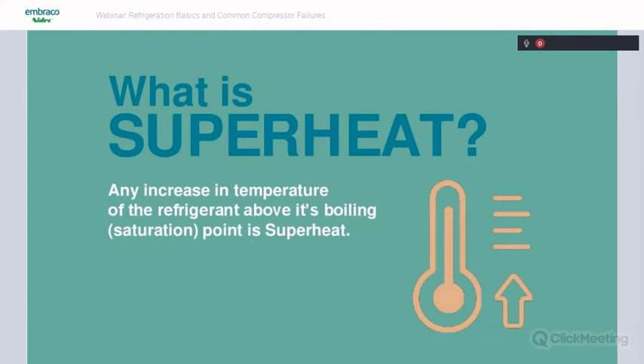Like right now, what is superheat? Superheat is any increase in the temperature of the refrigerant above its boiling point. We also call that boiling point the saturation point. So anytime a liquid gets enough heat in it to where it boils, that's what we call the saturation point. And you can use that to charge a system. Typically, we're going to want to use superheat in a fixed orifice system, because we'll talk about that in a second when we talk about subcooling. But basically, that's what superheat is. We measure the temperature of the refrigerant above its boiling point.